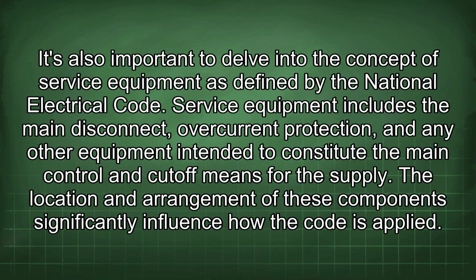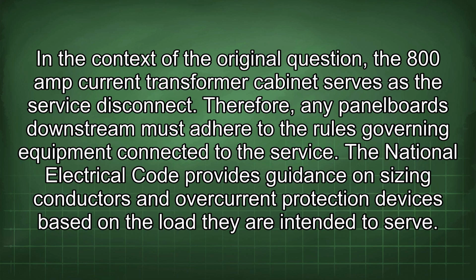It's also important to delve into the concept of service equipment as defined by the National Electrical Code. Service equipment includes the main disconnect, overcurrent protection, and any other equipment intended to constitute the main control and cutoff means for the supply. The location and arrangement of these components significantly influence how the code is applied. In the context of the original question, the 800 amp current transformer cabinet serves as the service disconnect. Therefore, any panel boards downstream must adhere to the rules governing equipment connected to the service.